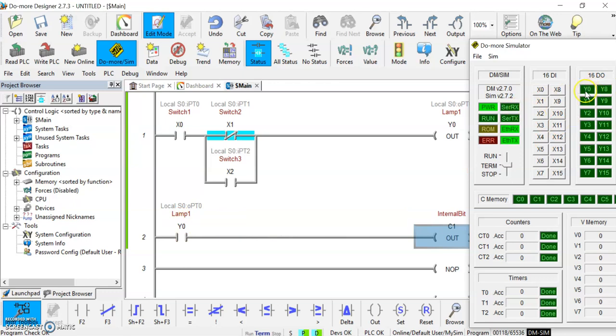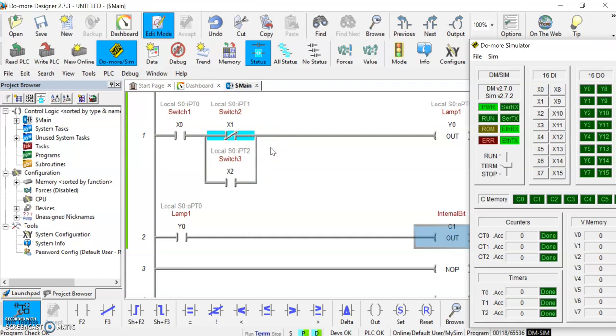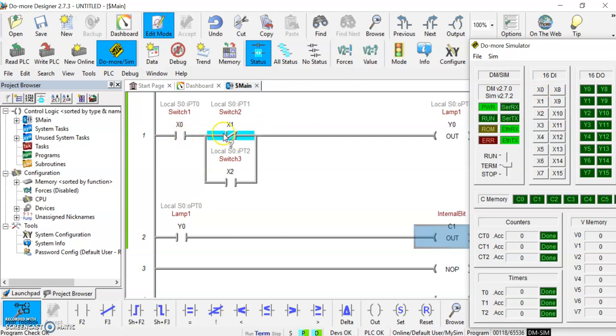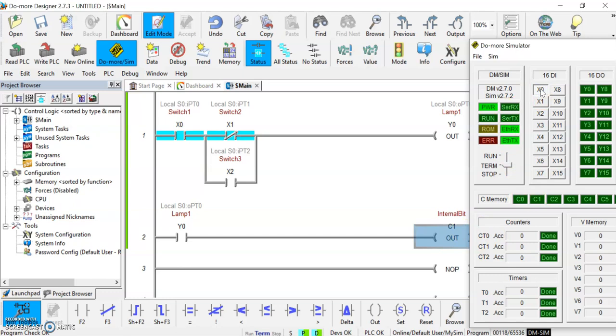Now let's start activating some switches here. This is already happy because it was looking for a switch opening and it sees that already, because this X1 hasn't been pressed down. If I press it down, you're going to see that that blue line goes away. Okay, so it's not happy now. Let's put it back there and hit X0. So if you think about what's going to happen, this is going to go true, and so this whole top portion of the rung is going to go true. This should light up and write a 1 there and should write a 1 there and should write a 1 there. So then we'll be looking at this light and this light, or sorry, C1 lighting up. Oh okay, made a first mistake. Let's switch this to run mode. If you don't switch it to run mode, nothing's going to happen.